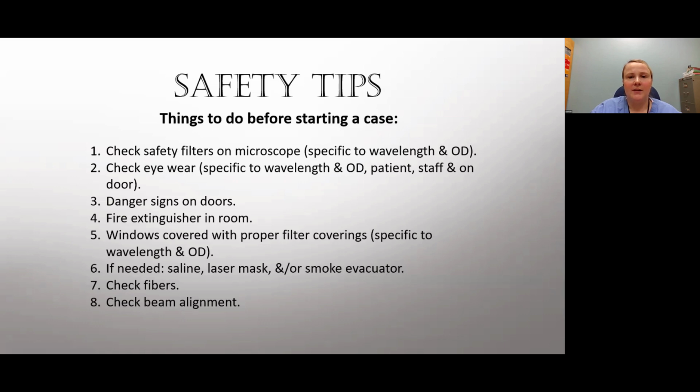Check your eyewear specific to wavelength and OD. Sometimes your patient might need eyewear depending on the procedure, and make sure your eyewear that's specific to wavelength and OD again is on the door. Make sure your danger signs are on the door. Also make sure the fire extinguisher is in the room. Make sure the windows are covered with proper filter coverings. Again, they're specific to wavelength and OD. You can get filters, you can get curtains, you can get blinds, depending on what your facility would like to have or what's best needed.